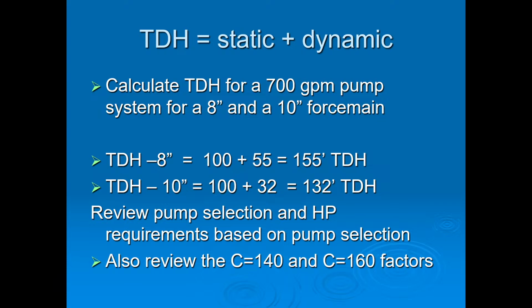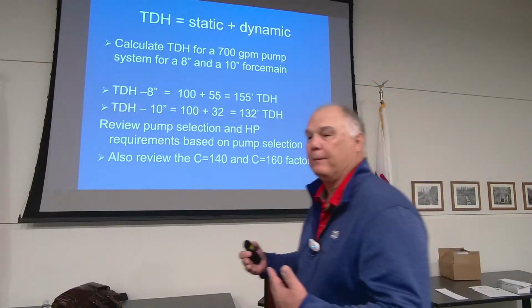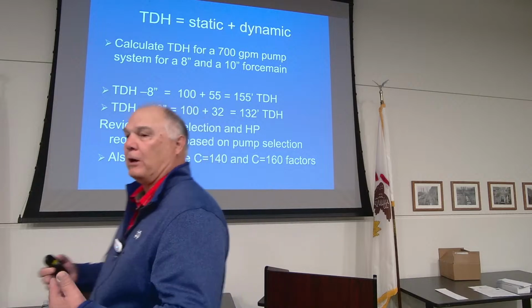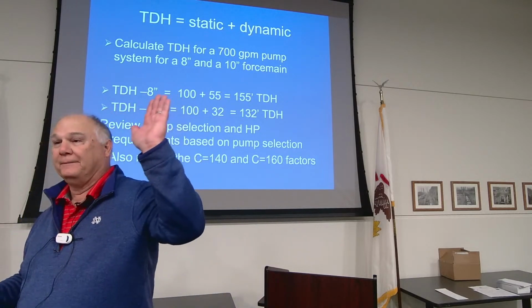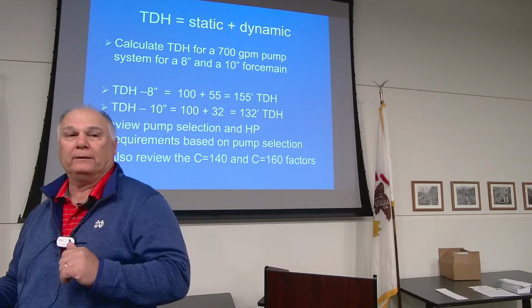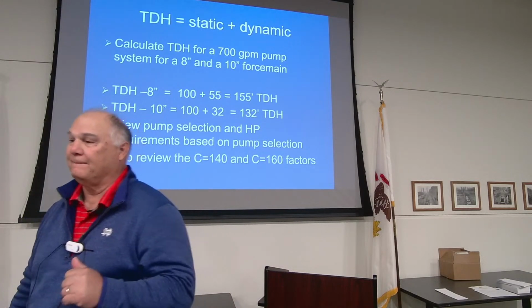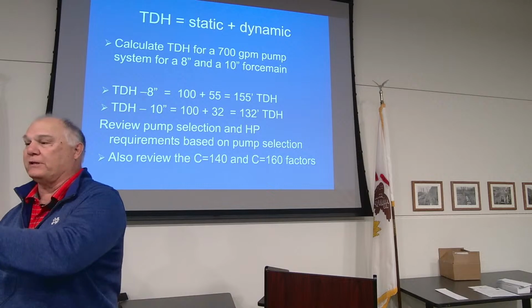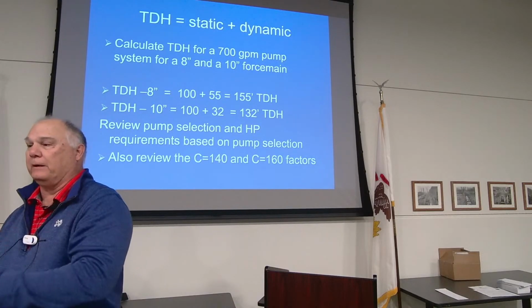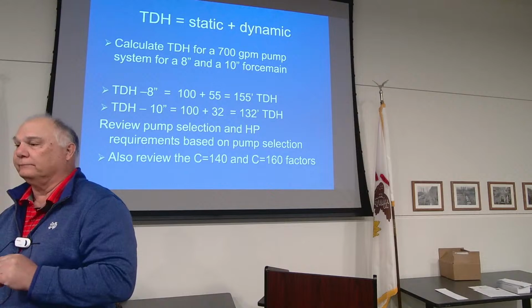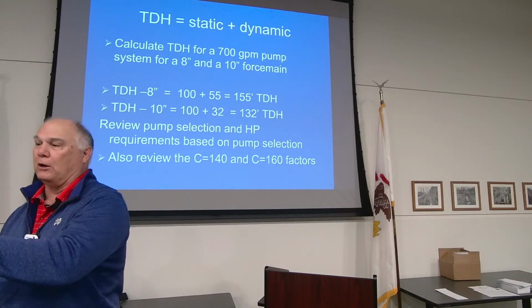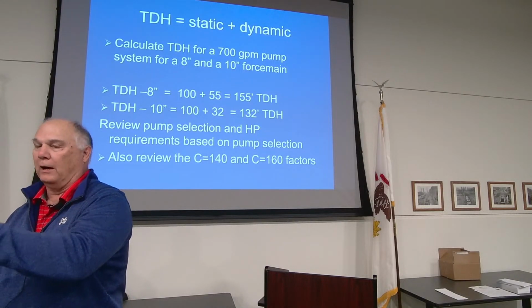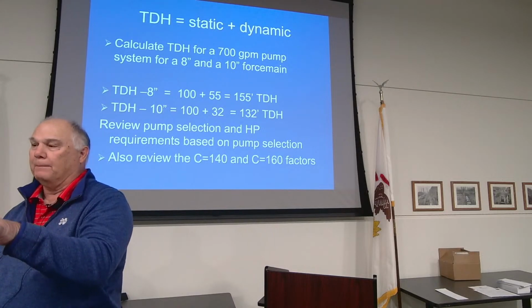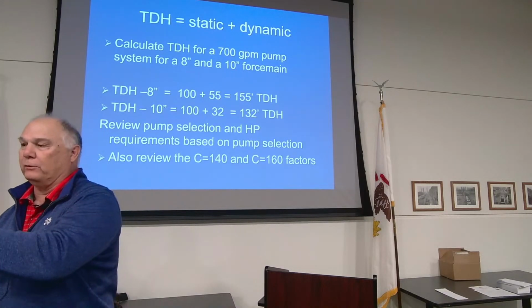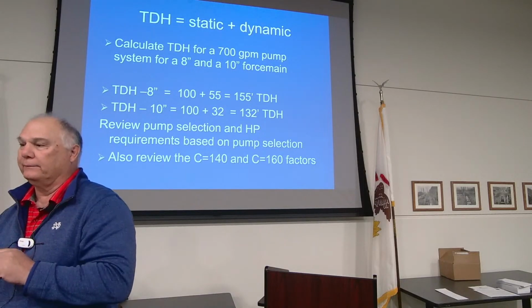So how many people call their lift stations by their real name, what they should call them? How many people call them Fourth and Main, or by the street name that they're at? Yeah? What should you do? You should say Fourth and Main's pumping 700 gallons a minute at 100 foot of head. Therefore, you'll always know, because you always have some records somewhere on where you're at and what you're doing. But pumps always give you a gallons per minute at a certain head from that particular point.